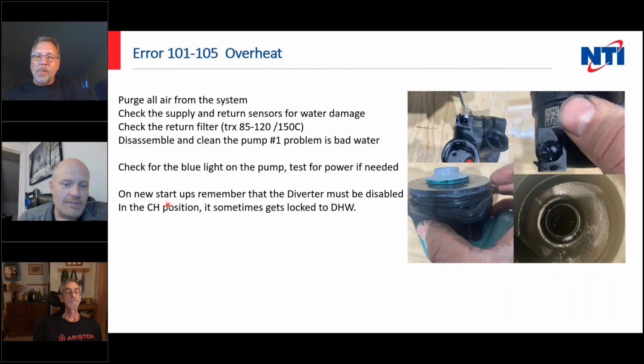On new startups, if you're not using the domestic, or even if you are using it, watch that diverting valve. Sometimes it gets locked in the wrong position due to pressure differences, air locks and things like that. Make sure the diverter valve is working, and also, again, if you're not using the diverter valve, make sure you've disabled it correctly, because if you don't, you could be deadheading your boiler pump.